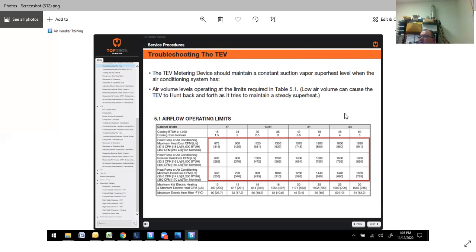We'll cover a little bit of TXV here. The TEV metering device should maintain a constant suction vapor superheat level when the air conditioning system has proper air levels. Low levels can cause the TEV to hunt back and forth as it tries to maintain a steady superheat.